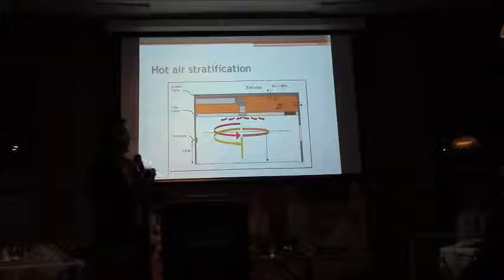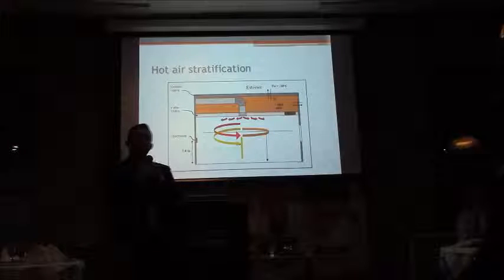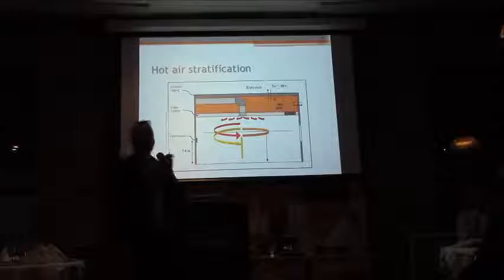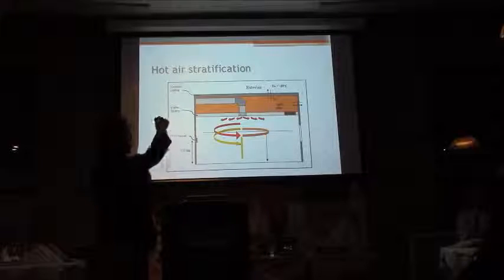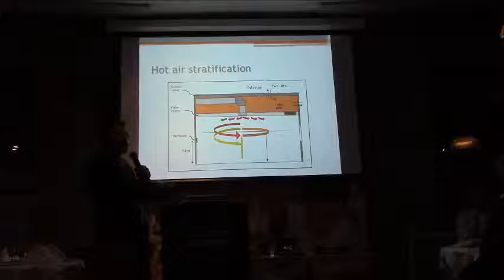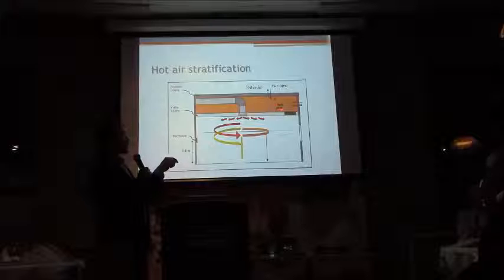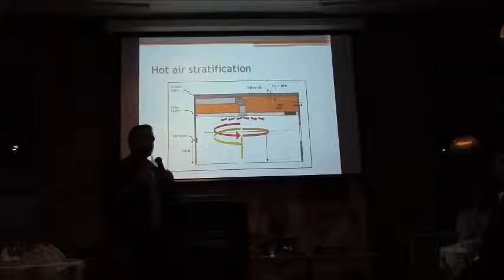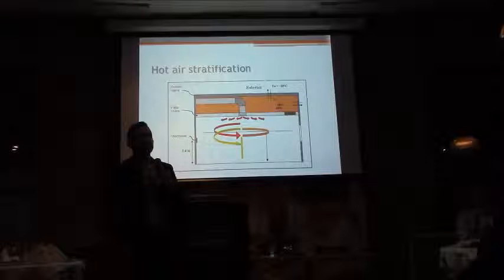Like I mentioned, the high induction diffuser has a swirling motion. If you compare it to a cone, the air comes out horizontally like that, while the high induction would come out swirling. And that swirling motion, combined with high velocities, allows your air to reach down into the occupied zone. So typically, you'll be able to reduce the air temperature inside your ceiling space from 28 down to 23. So all that hot air is recuperated and sent down into the occupied zone.